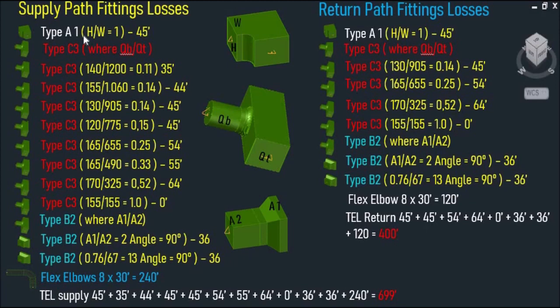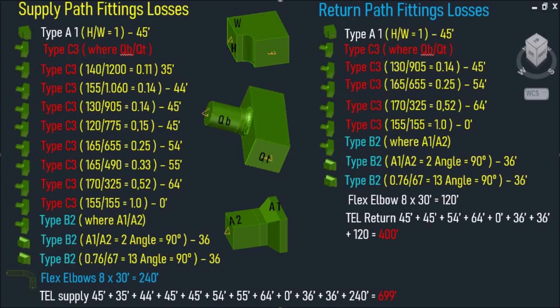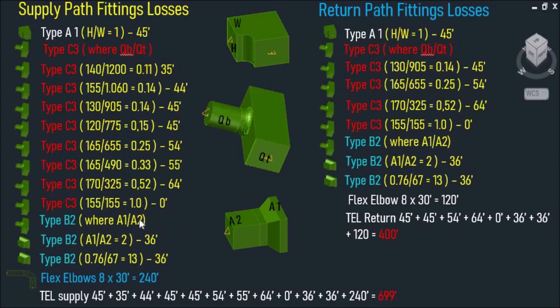I've already tabulated the types and quantities of our fittings. For fitting losses through our supply path: Type A, where height divided by width equals 1, gives a total equivalent length of 45 feet. Type C3, where QB over QT equals 140 CFM over 1200 CFM equals 0.11, gives a total equivalent length of 35 feet. Type B2 over A1 over A2 gives a total equivalent length of 36 feet. Adding all numbers including flex elbows gives a total equivalent length of 699 feet for supply. The return side comes out to a total equivalent length of 400 feet.